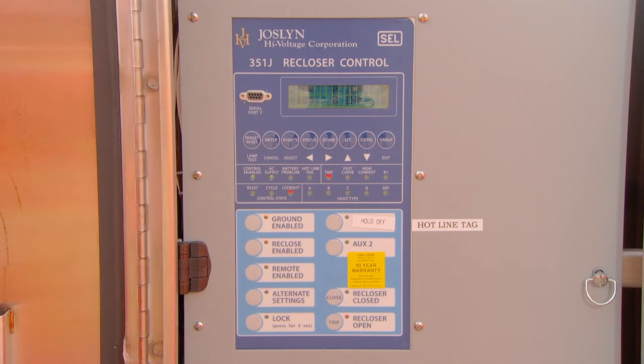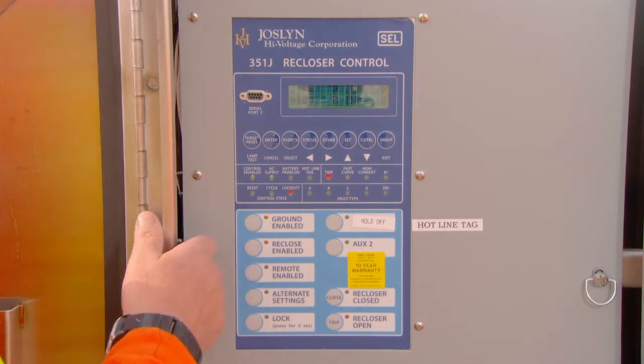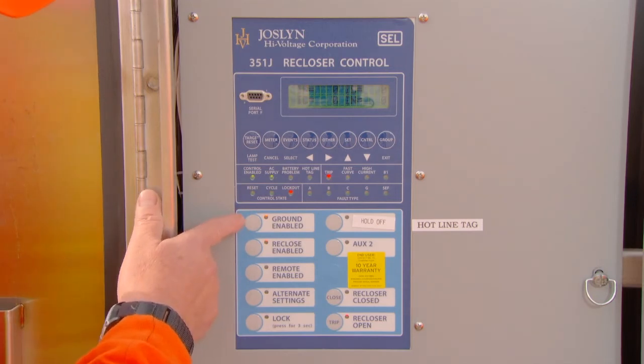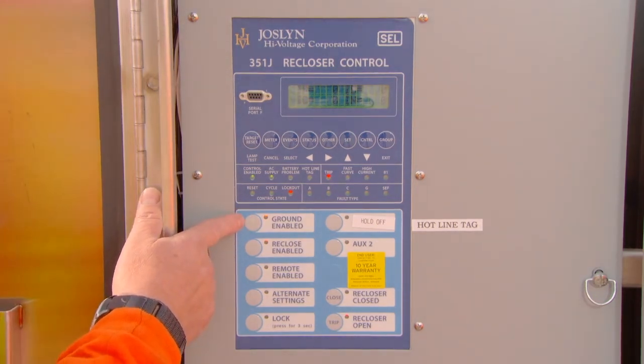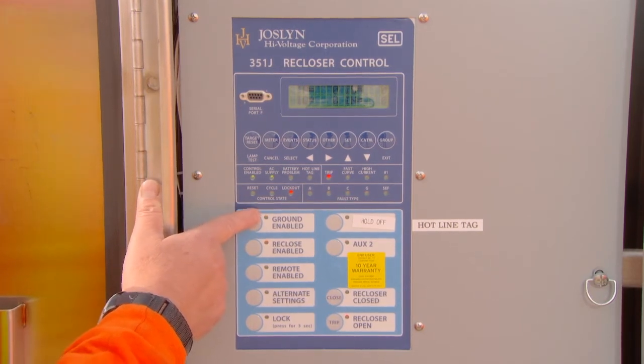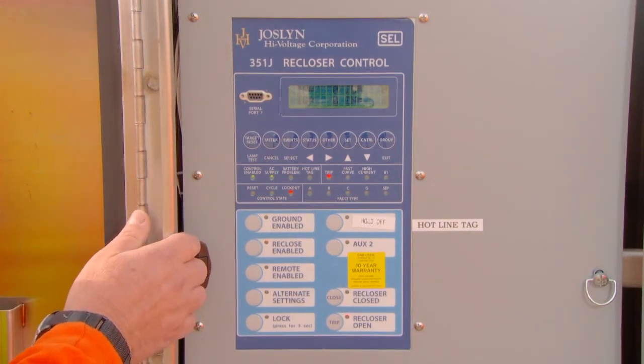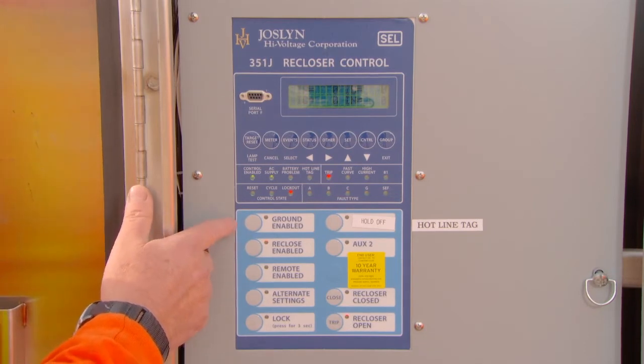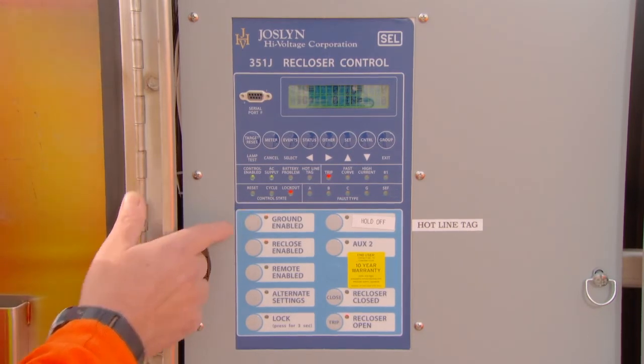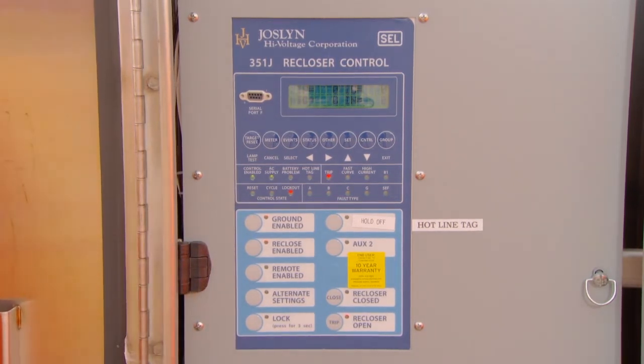Below the status LEDs are another set of push buttons. First, we have the Ground Enabled button. To turn off the ground, press this button and you will see the amber light turn off. The ground is now disabled. Press this button again to enable the ground. This is typically for testing and/or switching procedures.